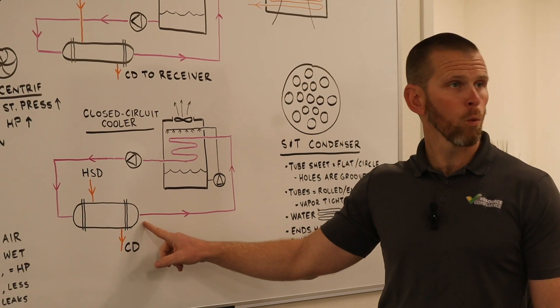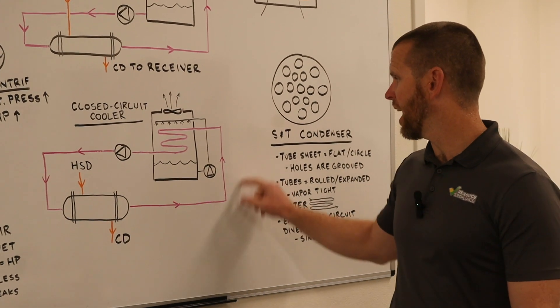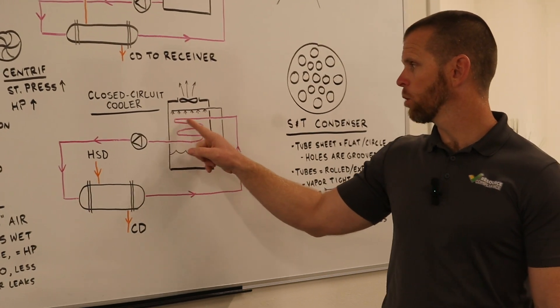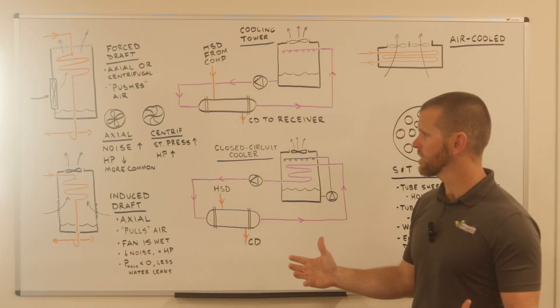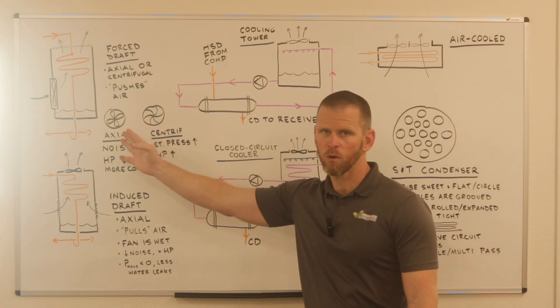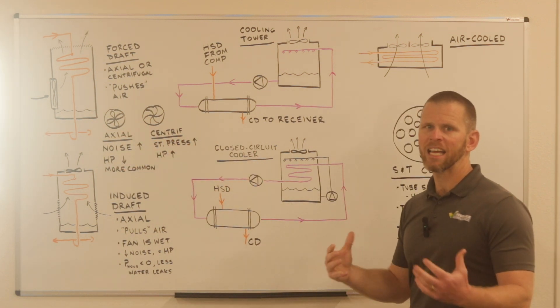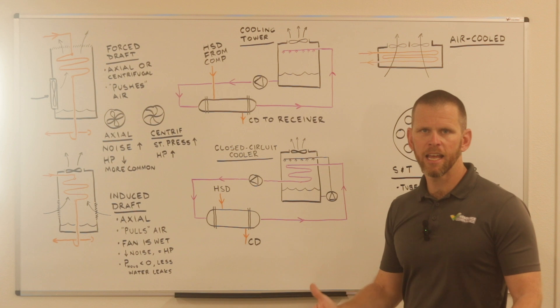A cooler temperature enters, a warmer temperature leaves, and so we bring it up to our closed-circuit cooler, and we circulate through this. This closed-circuit cooler operates very similar to the evaporative condenser we've already looked at, but we don't call it a condenser because nothing is being condensed.